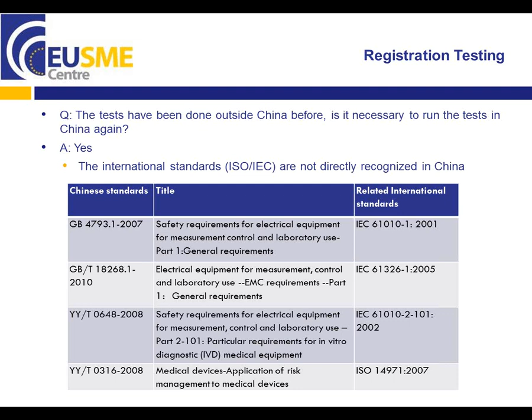So we're going to show you how a registration test is done in a Chinese lab. To run a registration test, the manufacturer shall first draft the documents about the product technical requirements. Then you also send the product samples to the lab. The test lab will then test the product according to the product technical requirements and release a testing report. The product technical requirements and the testing report shall then be put into the preparation for registration and submitted for CFDA review. Next slide, please.